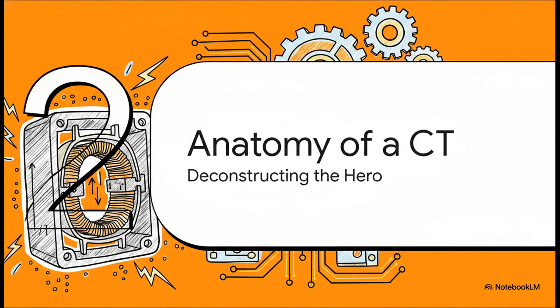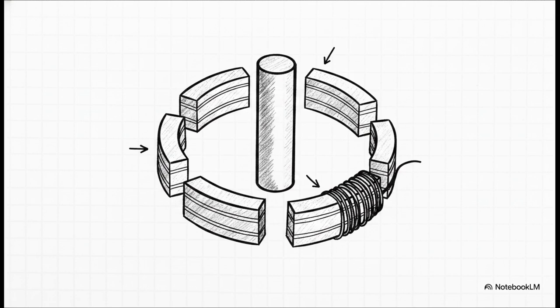Moving to Section 2, anatomy of a CT. Let's deconstruct this silent hero. A CT might look like a heavy hunk of metal from the outside, but it's a super precise instrument built from three main parts. First, the primary winding. This connects right into the main circuit. Actually, in a lot of industrial setups, this isn't even a separate wire, it's just the main conductor itself, like a thick bus bar passing straight through a hole in the middle.